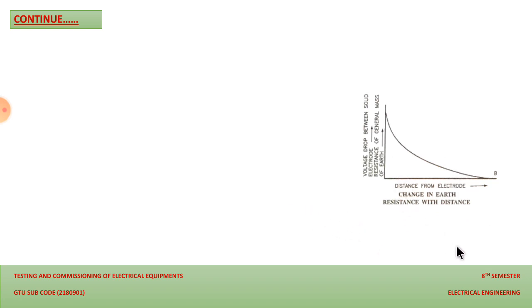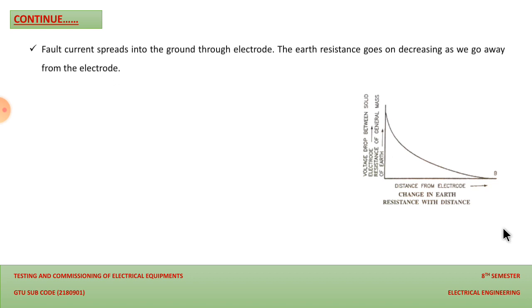So in this diagram you can see the change in the earth resistance with distance. Here the x-axis denotes the distance, and the y-axis denotes the voltage drop between the solid electrode and the general mass of the earth. You can see that where the distance is less, the voltage drop between the solid and earth electrode will be more. And as the distance from the earth electrode increases, the voltage drop gradually decreases. So this is how the earth resistance affects things, and this is the factor that we should keep in mind while providing earthing to any electrode.